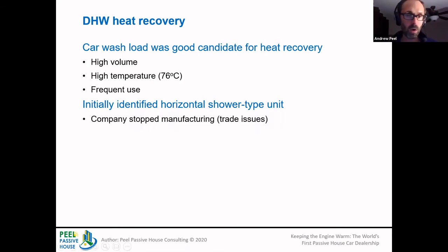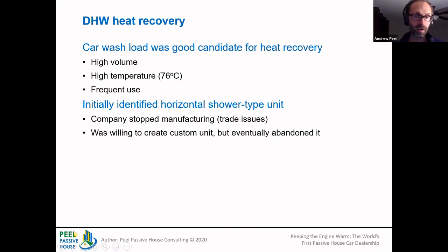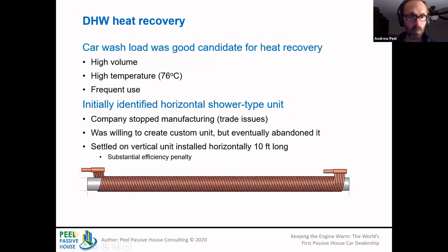And we found a manufacturer in Canada that was at one point producing these. They stopped producing them because of trade issues. We didn't get a really clear answer about that. They were at the beginning willing to create a custom unit, but then midway through they said no, we're not going to do that. I don't know if, again, these trade issues came into play. So unfortunately, we didn't have an option for that, and we settled on taking a vertical unit, one you would normally install vertically, and installing it horizontally under the drain of the hot water car wash bay, and so we recovered heat there.